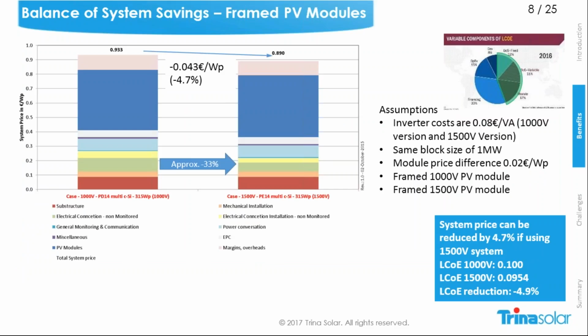The first example is still here, with the system costs marked as green. Here we are comparing a 1000 volt module framed versus a 1500 volt system framed. You can see that the module costs, it's harder to see, are a little bit more expensive. You clearly see the savings for the cabling and electrical connections. The substructure, for example, and the mechanical installation are for sure not touched. Here the savings on the electrical components are approximately 33%.